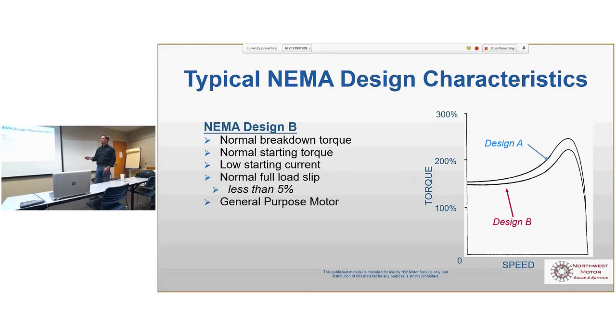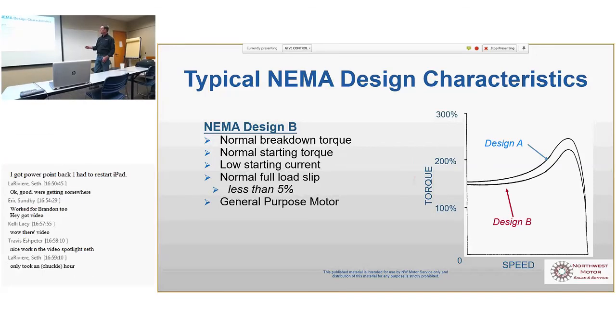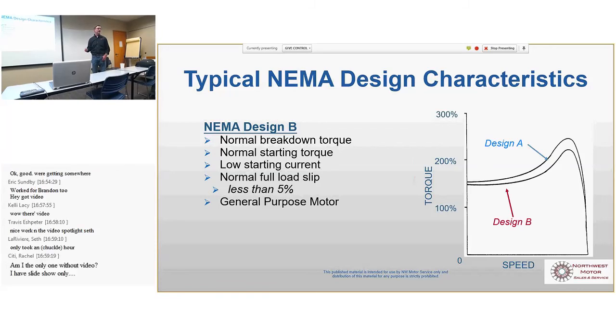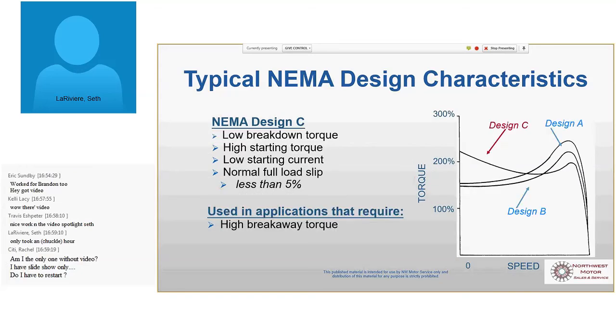So NEMA Design B is normal breakdown torque. It looks like this. It has a little bit lower starting torque than the A, but it has correspondingly less current too. So it doesn't draw as much current, because current and torque are proportional. If you need a lot of torque, you got to have a lot of current to do it. So this has a little less current on startup. It's just a normal, what they call the normal profile. It's usually about 2% slip. They're just defined as normal duty motors.